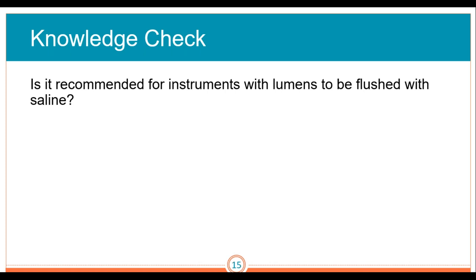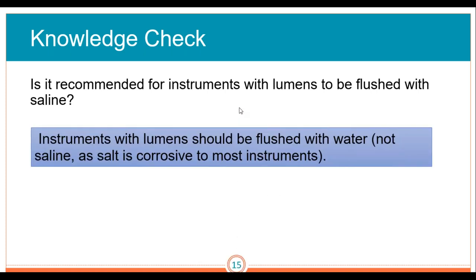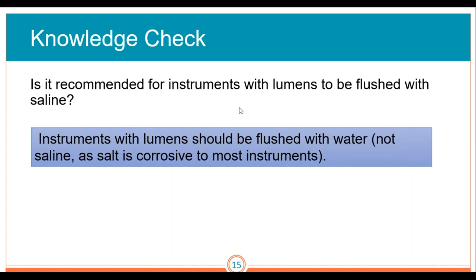Knowledge check: is it recommended for instruments with lumens to be flushed with saline? False — you should not do this. Saline is corrosive to our instruments. We want to make sure we're using sterile water to clean these instruments. Please do not use saline.